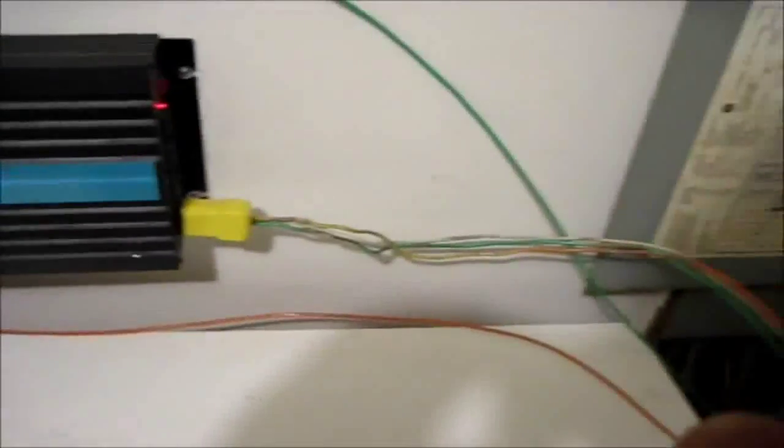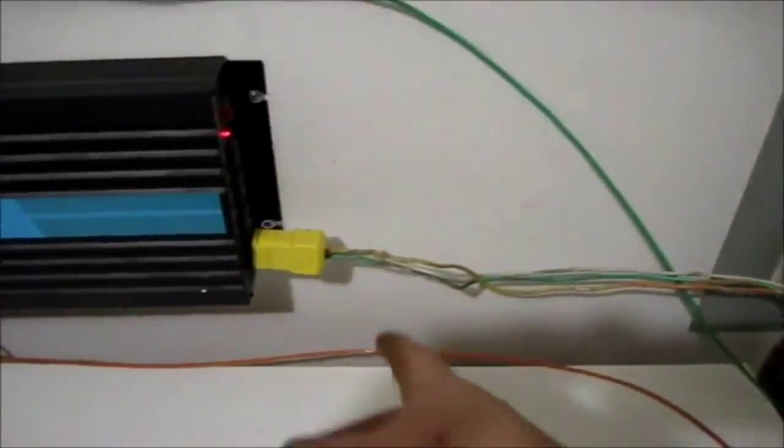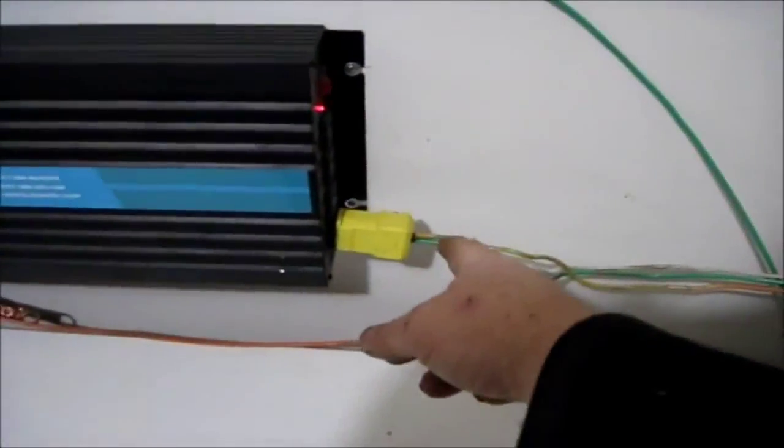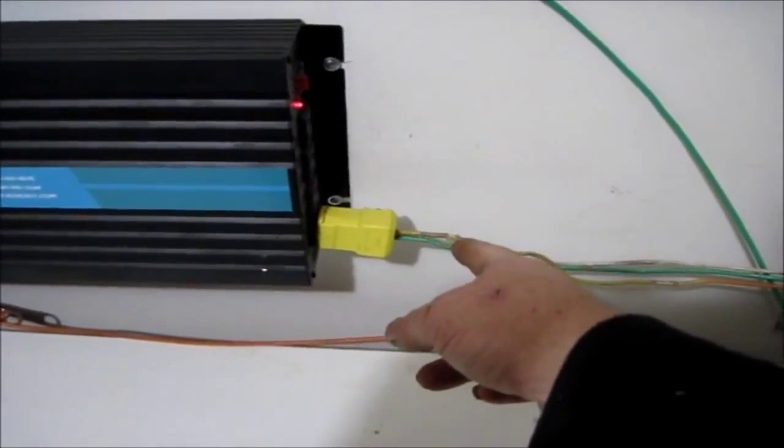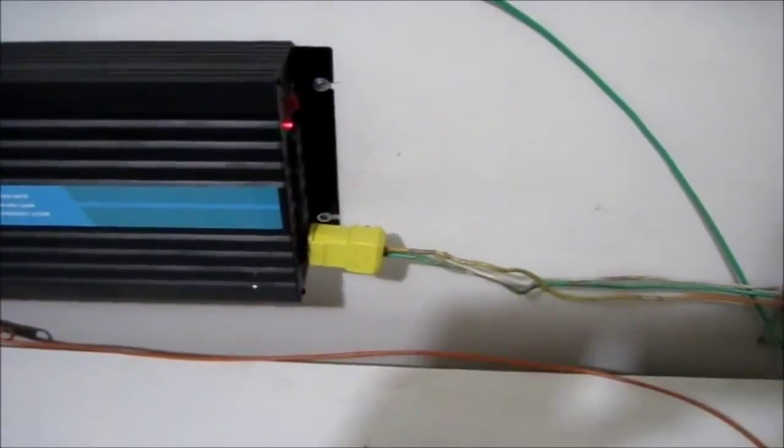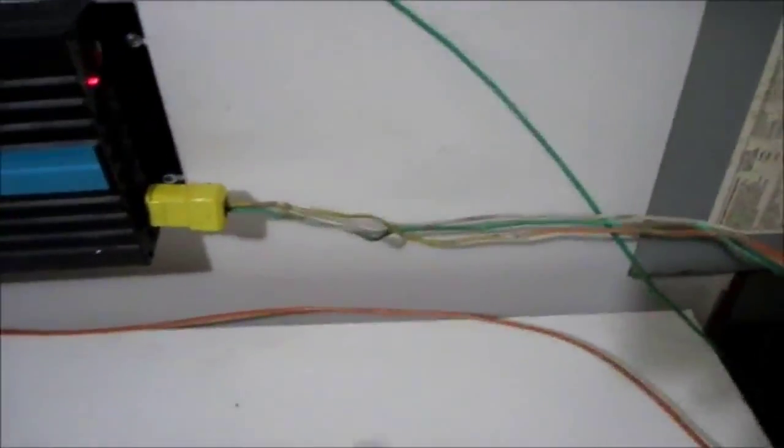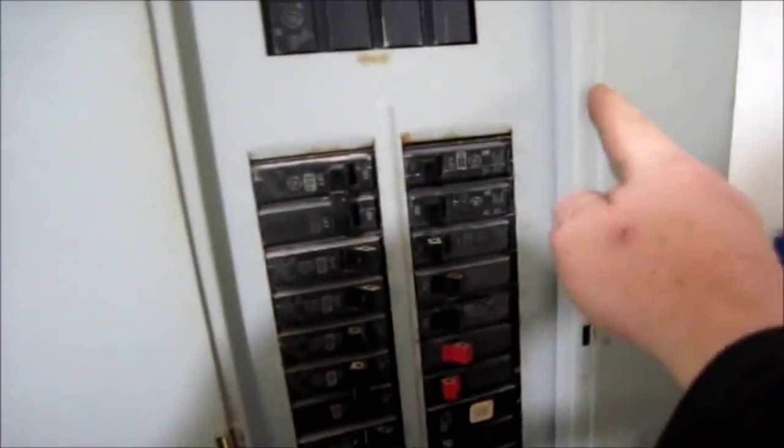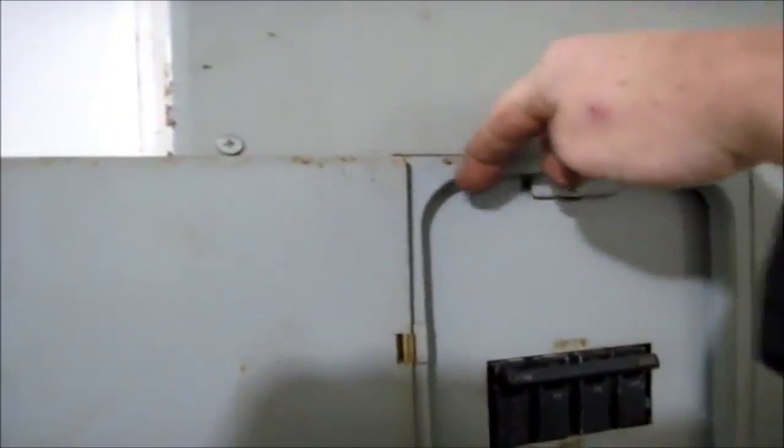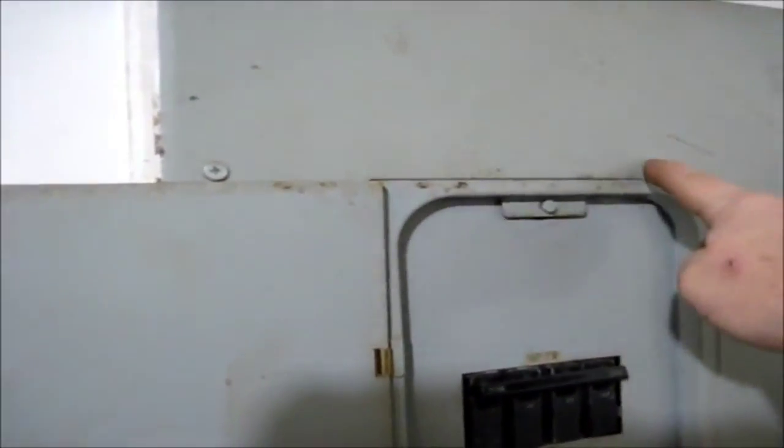I only have one light on. To show you how I have it into my house going to my panel, it's just a green, white and orange wire. The white wire is going over to a little bus bar over here, the green wire is to a bus bar here, and then the orange wire is going into the top two lugs that your actual power would hook up to.